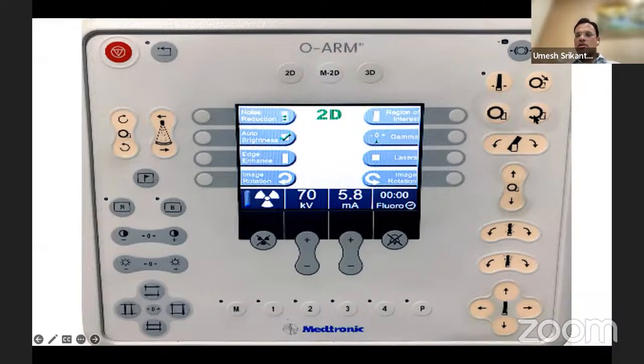So as you can see, this is to open the ring of the O-arm, and this is to close the ring of the O-arm. The O-arm can be tilted in case you want the angle to be correct. This is to move it forward and backward, and then this is to change the angle of the O-arm as a whole. These are for the stand, whereas this is only for the ring. And once the ring is there, you'll be able to make it into an AP and a lateral image based on the rotation of the scanner that is inside the bulk of the O-arm.